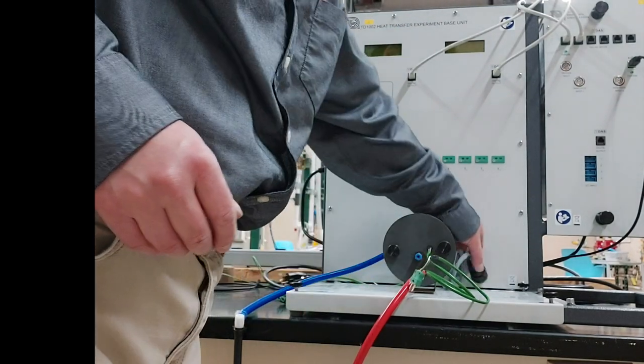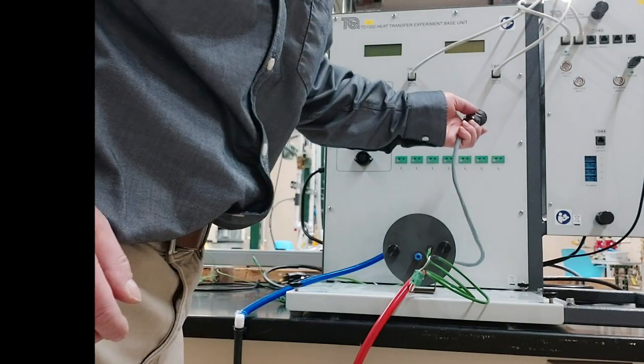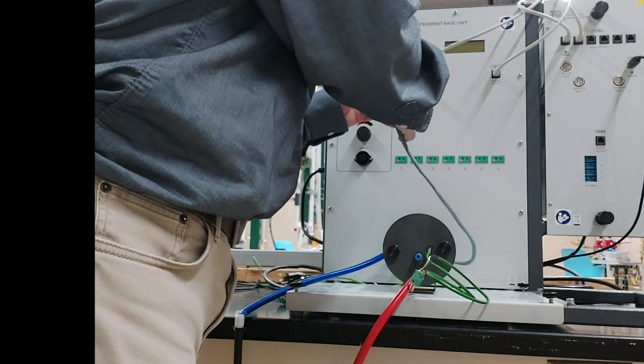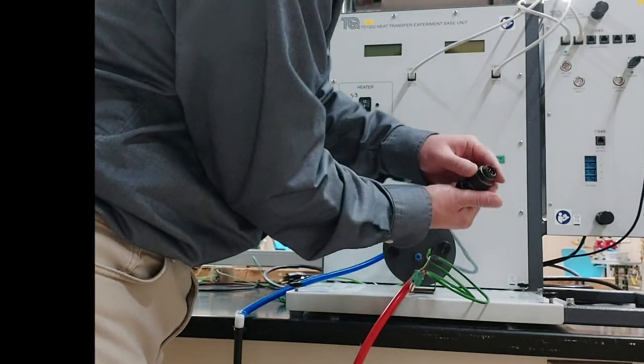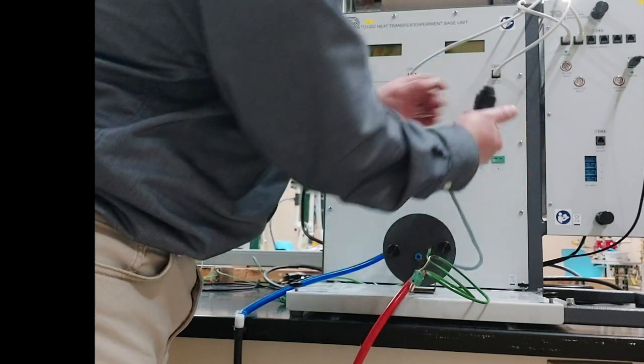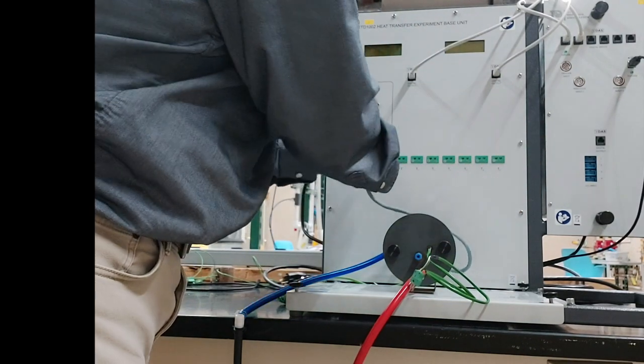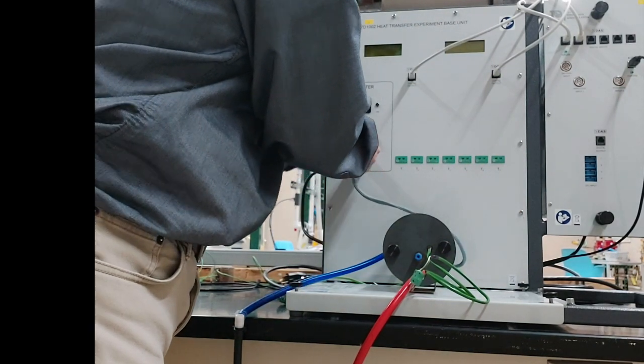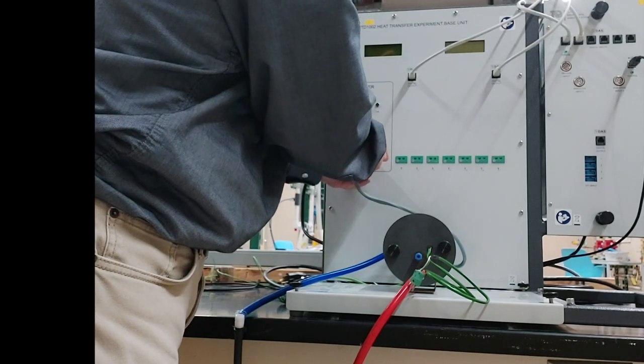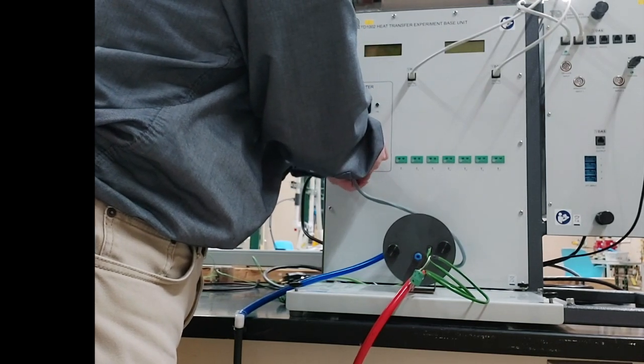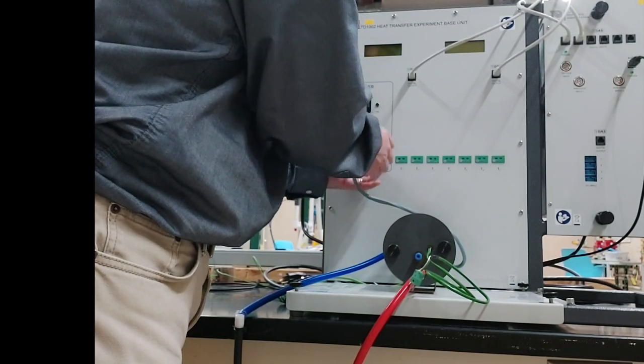Connect heater's power cable to the control panel. There is a notch in the plug that should be aligned with the corresponding notch in the receptacle. Push it in, hold the plug piece close to you, and turn the other plug piece close to the panel clockwise.